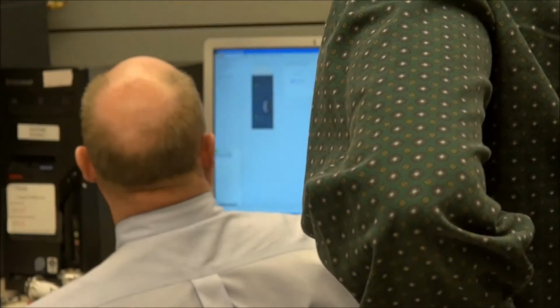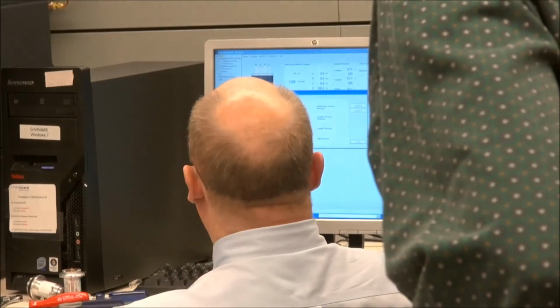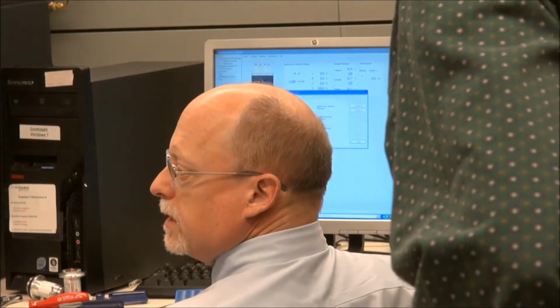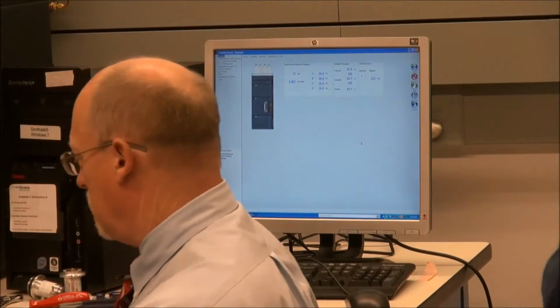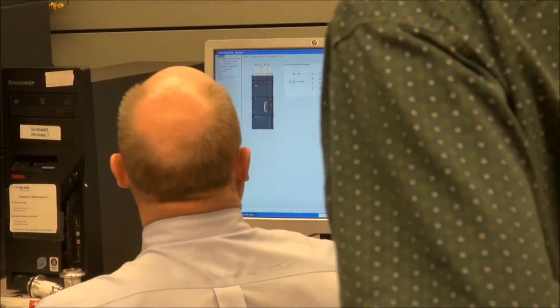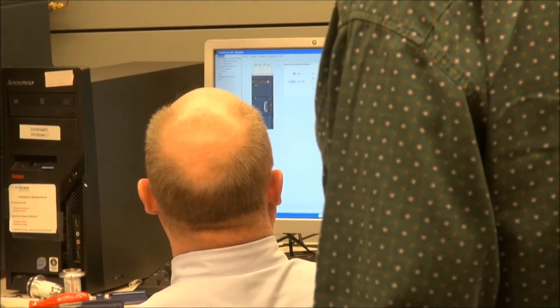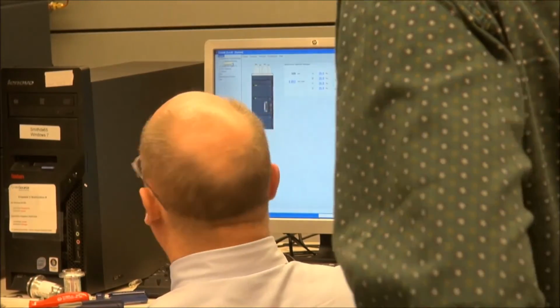At the top of the level, at the system top level control, see leak sensors? Okay. I can enable and disable all my leak sensors from here. I think we had a visitor. Who's that? So, that's convenient. Turn it on and off.